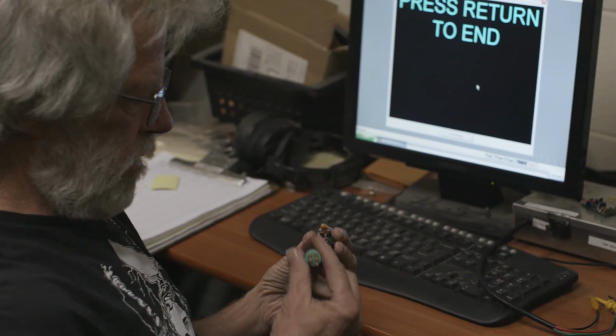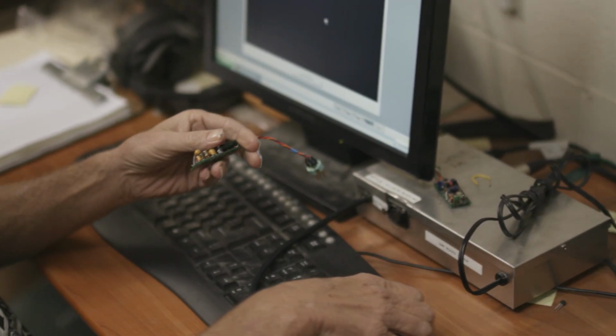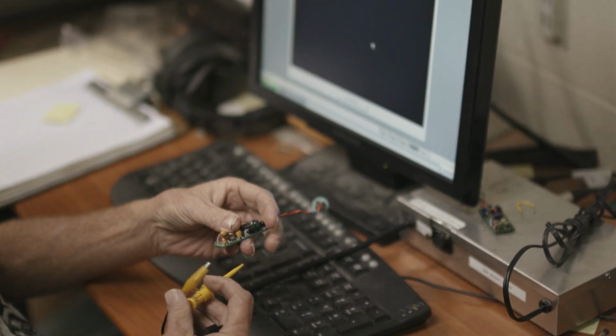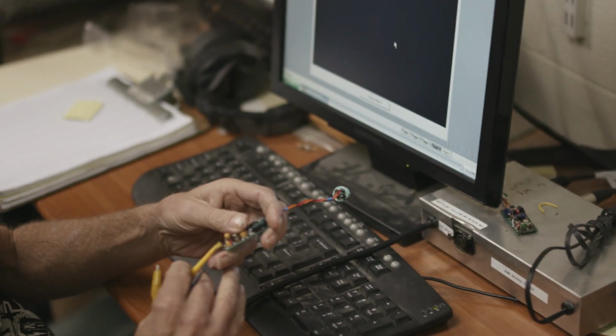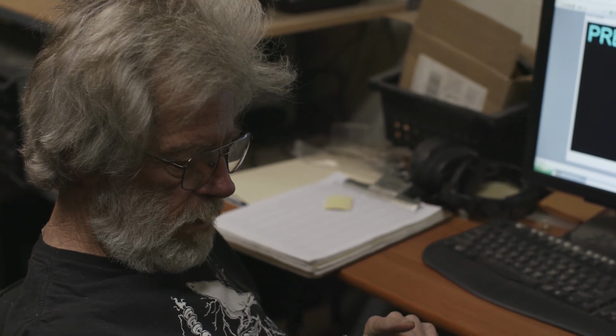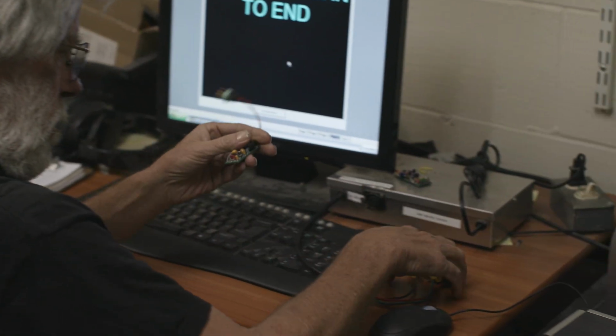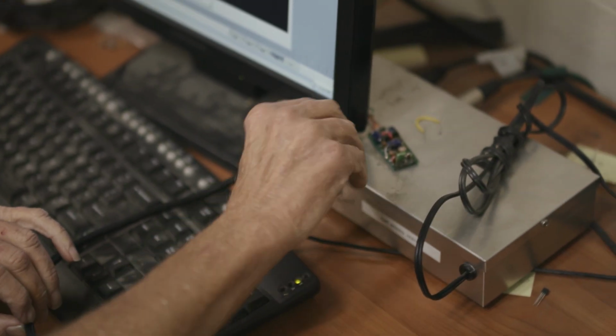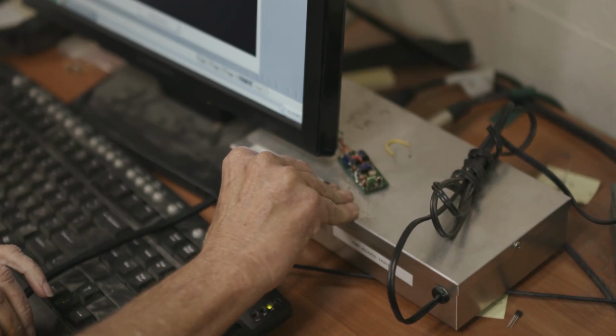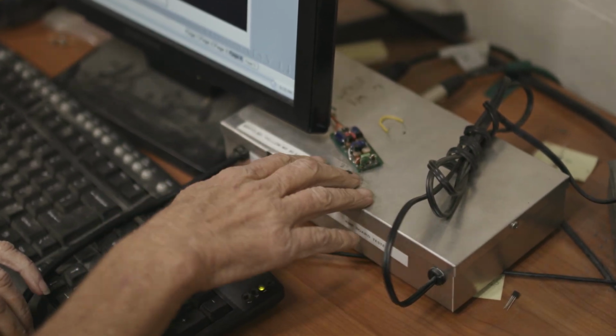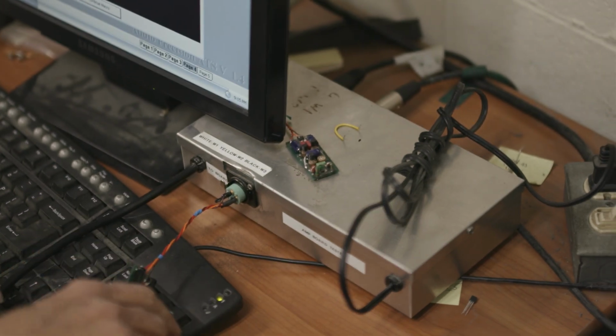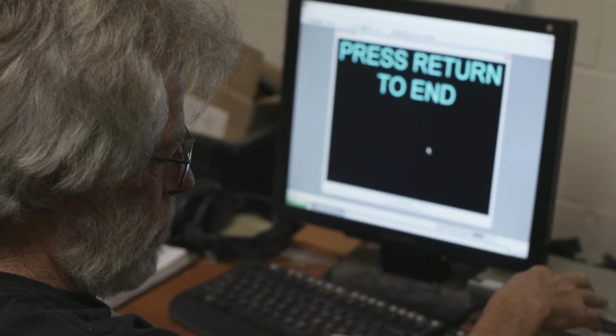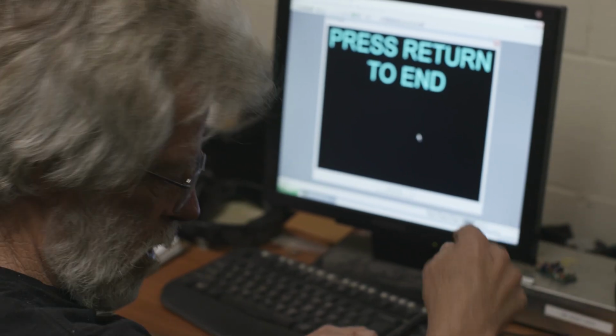This switch switches between testing microphones and testing circuit boards. There are standard operational tests we do on the circuit boards: frequency response, distortion, and gain. This unit gives an unequivocal indication of what's happening. We plug the circuit board in - since these are phantom powered, this box provides phantom power and keeps the DC phantom power off the input of the test set.